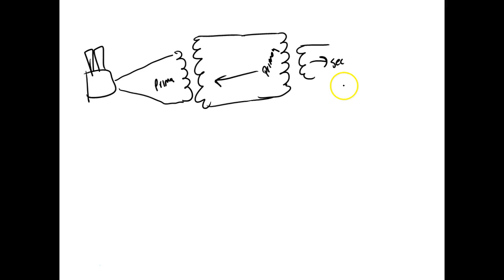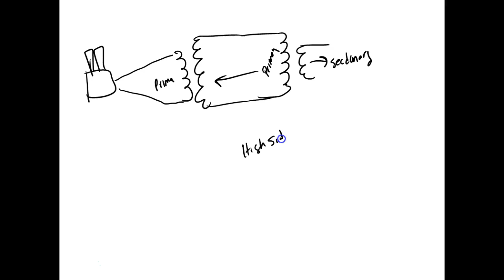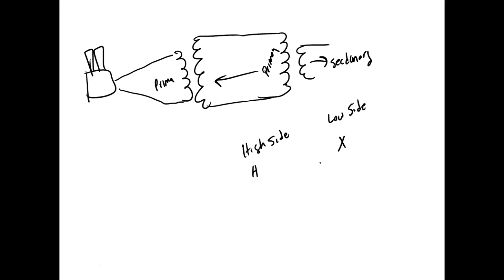Industrial transformers aren't rated primary and secondary, because as long as you don't exceed the insulation voltage, you can hook them up either step up or step down. So they're labeled high side, where your high voltage is attached, and low side, which is your low voltage. They label the leads with H's, and here with X's. They don't use L's, because L's were used by inductors. So if you look at the layout of a transformer, you can tell from the leads.